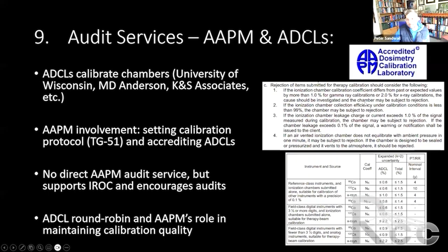So if a particular calibration laboratory, when we talked about that round robin, comes back with a chamber that's 2% different from the other laboratories, their processes will be subject to scrutiny and will be investigated, and they'll try to bring them back in line. But again, the AAPM in the States has a very clear role in setting the quality standards for these calibration laboratories.